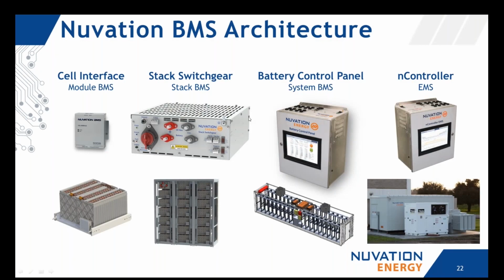To show the different levels of our BMS, it starts at the module level, and this is our cell interface, measuring voltages, measuring temperatures, and doing balancing. That rolls up to our stack switchgear, which is the stack BMS. It's built around our stack controller, and it combines that with contactors, current shunt, fuses, manual disconnects, fan control, all the things you'd want on a stack level. And then for multi-stack systems, that rolls up into our battery control panel, and that's the system level BMS. It's built around our multi-stack controller and combines that with a wall-mounted unit with a touchscreen, networking, and UPS capability.